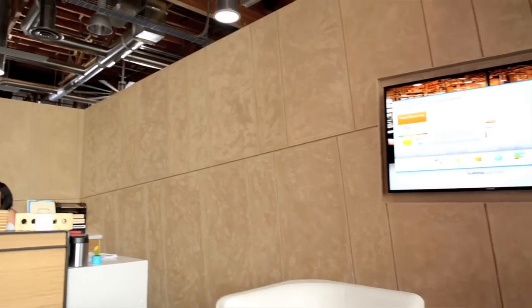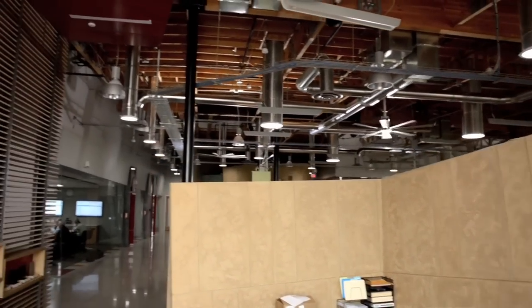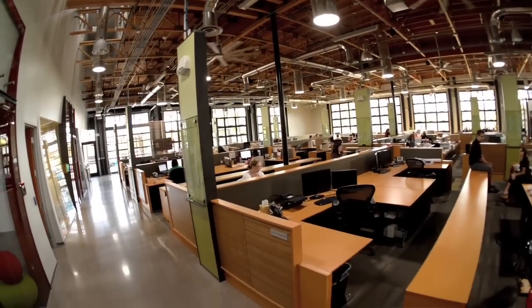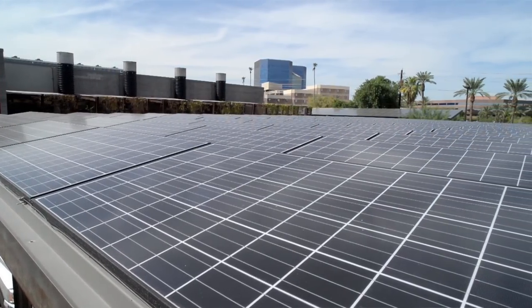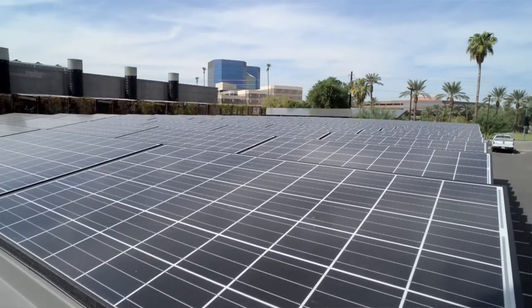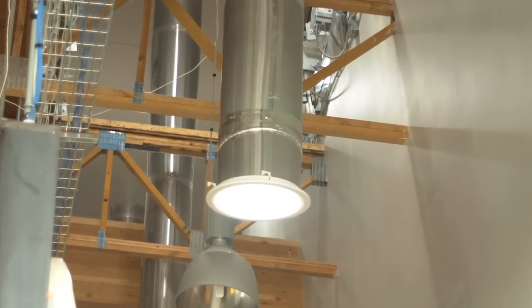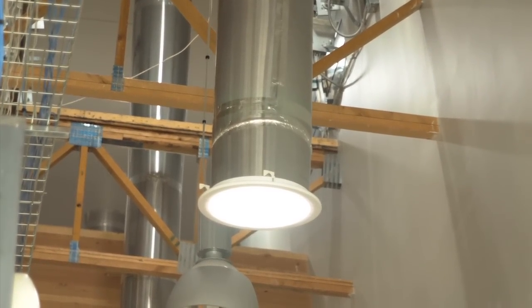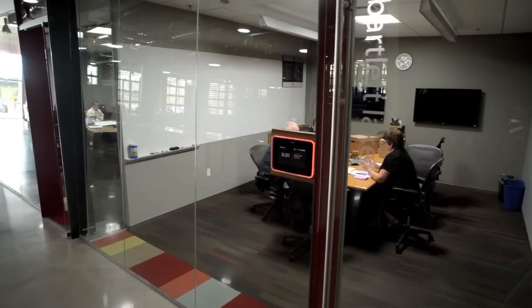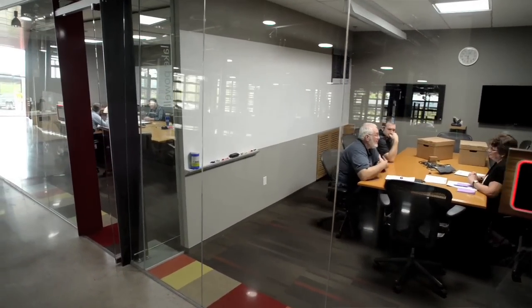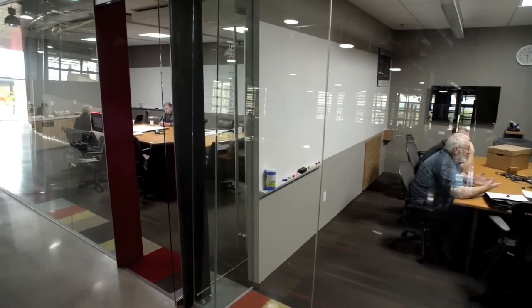Sizing the systems and understanding the loads in the building was probably one of the biggest technical challenges, because as we came up with one solution for one thing, it might drive up the electrical requirements, meaning the PV system had to go up. But then as we realized we're not going to use lights during the day, that drove down the electrical requirements. So the PV solution was actually one of the last solutions we came to, because until we finished the layout and understood where all the people would be, how many tubes we'd have, how many desks and conference rooms there'd be, and what lights could be LED versus fluorescent, all those decisions went back and forth.